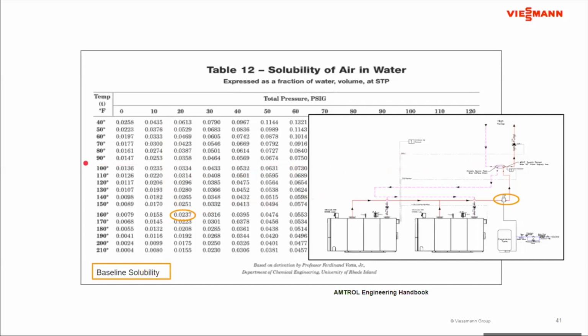So when we start to look at the location for the air separator and how it shows up in the drawings, typically it shows up here because, based on limited knowledge, the boiler side of the closely spaced T's of the hydraulic separator is going to be the best location from an aspect of pressure and temperature. However, out here, based on pressure, out here may be the best location. So really it's an application by application decision on where it needs to be. But from a drawing standpoint, we want to show the air separator in here so it goes in the boiler loop because it's the best generic location to work with. And that's why we show it there.